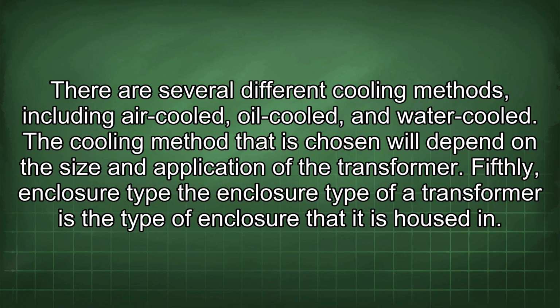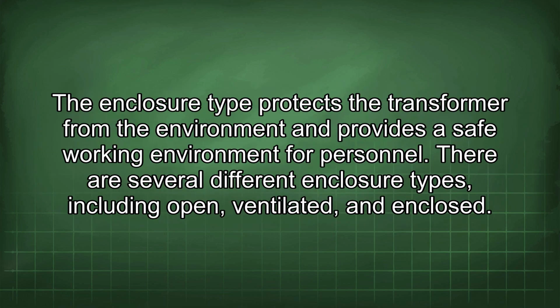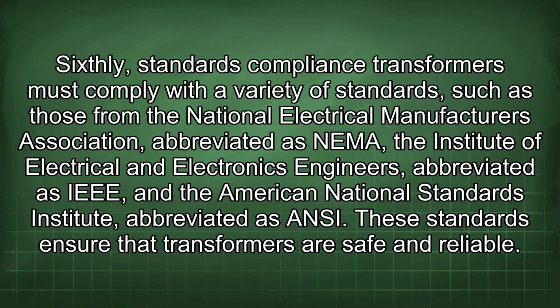Fifthly, enclosure type. The enclosure type of a transformer is the type of enclosure that it is housed in. The enclosure type protects the transformer from the environment and provides a safe working environment for personnel. There are several different enclosure types, including open, ventilated, and enclosed. Sixthly, standards compliance. Transformers must comply with a variety of standards, such as those from the National Electrical Manufacturers Association, abbreviated as NEMA, the Institute of Electrical and Electronics Engineers, abbreviated as IEEE, and the American National Standards Institute, abbreviated as ANSI. These standards ensure that transformers are safe and reliable.